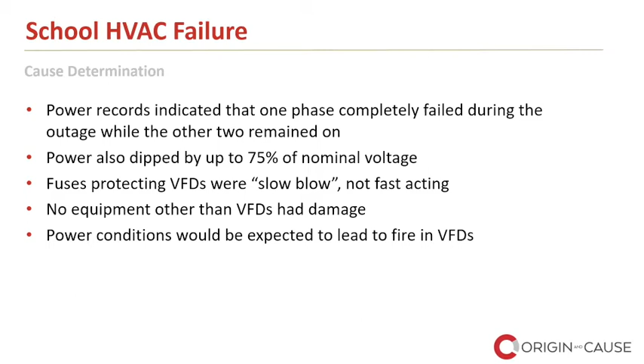But generally, it is standard practice to put slow blow fuses on circuits for motors because they have high startup currents. So when you first turn it on, they draw a lot of current for a very short time. These startup currents don't typically endanger the supply wiring, even though they exceed the nominal levels that the supply wiring is designed for, because they're very short duration. But they can expose equipment like VFDs to larger input variations than they can handle.